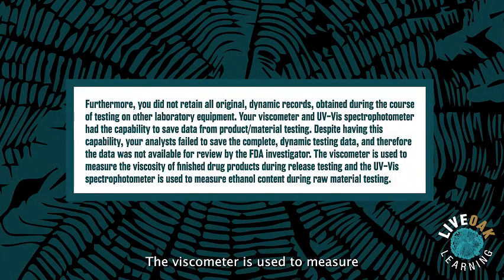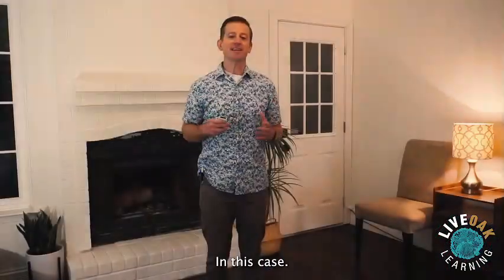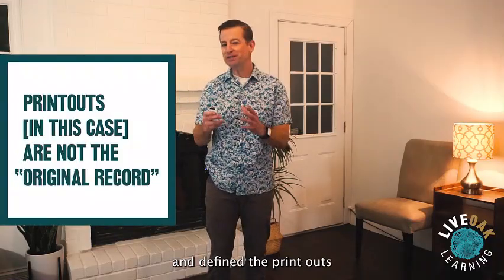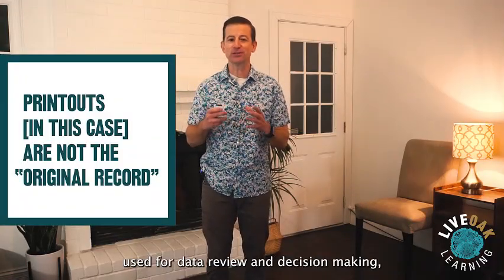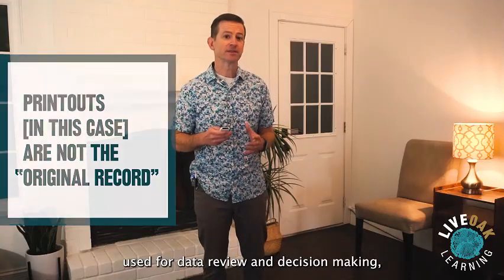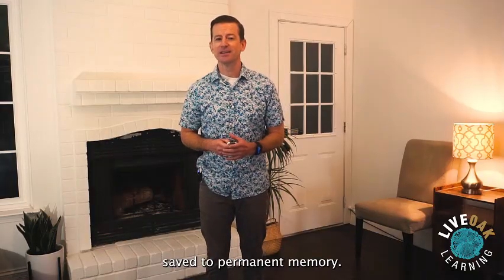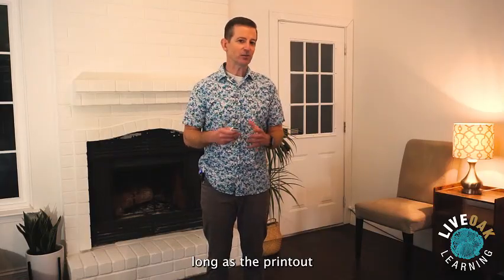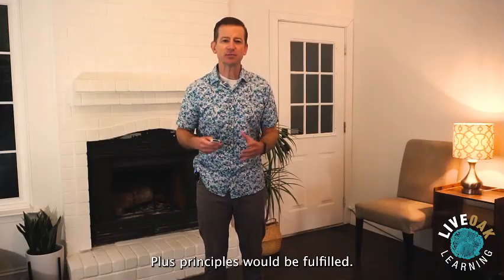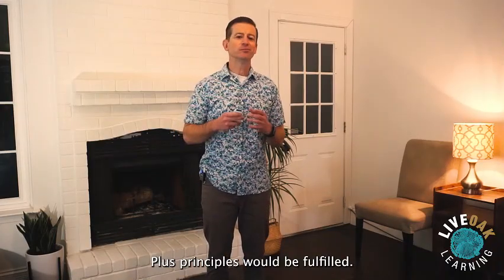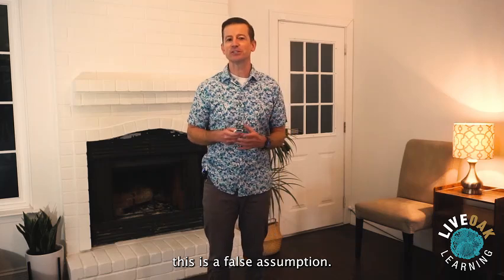The viscometer is used to measure the viscosity of finished drug products during release testing, and the UV-Vis spectrometer is used to measure ethanol content during raw material testing. In this case, the site most likely printed out the analytical results and defined the printouts as their original record used for data review and decision making, but failed to ensure the electronic record was saved to permanent memory. The site assumed that as long as the printout was available for inspection, the ALCOA Plus principles would be fulfilled. But as we have discussed, this is a false assumption.